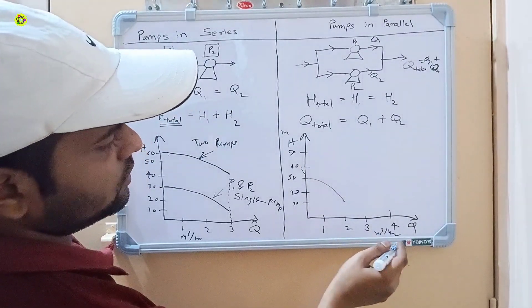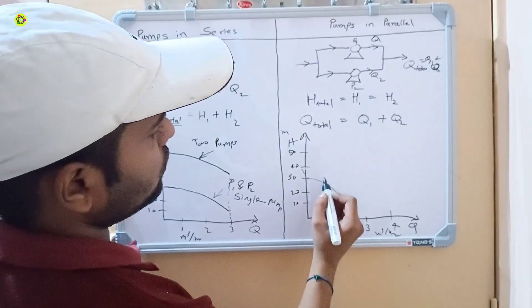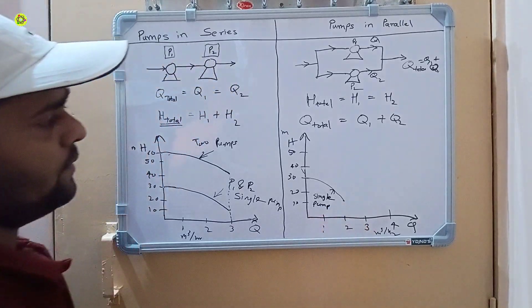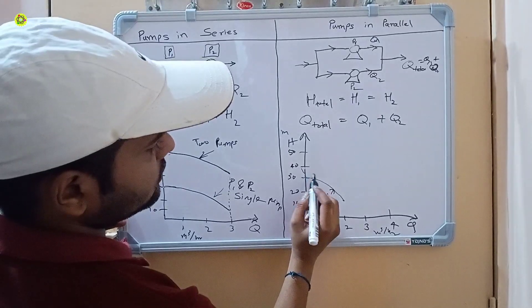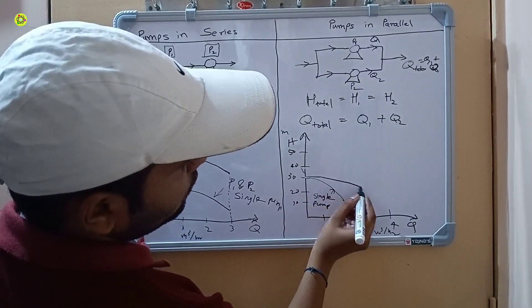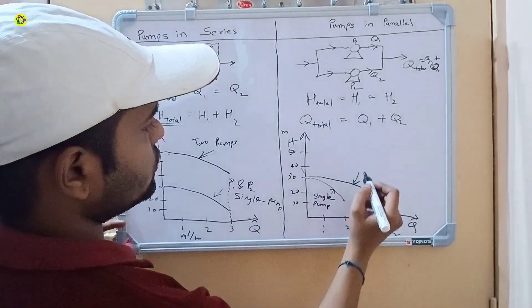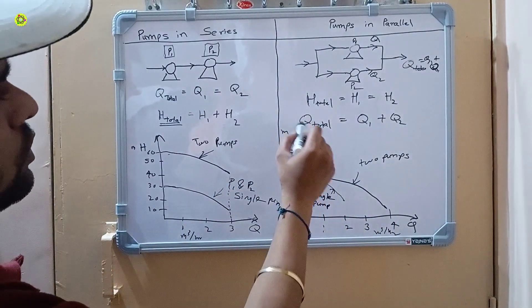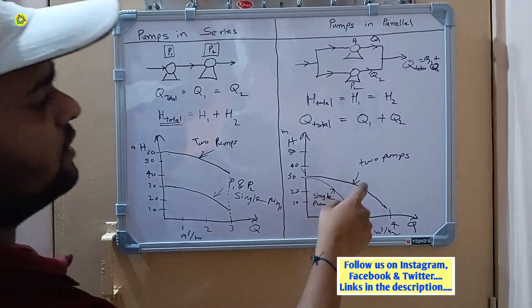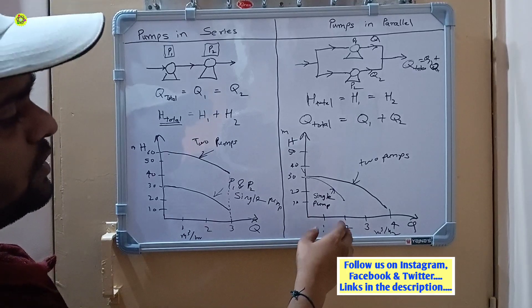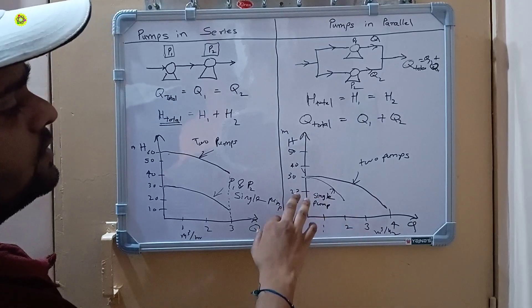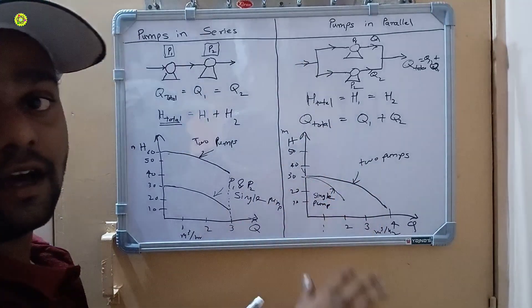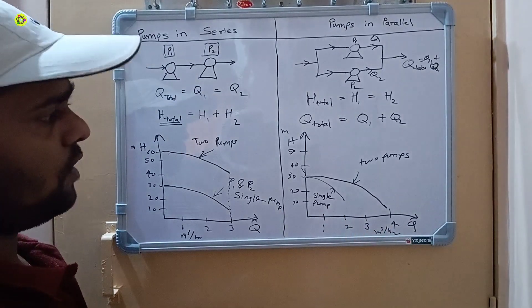For a single pump, the flow rate is about two meter cube per hour. For two pumps in parallel, the head remains constant but the flow rate increases to nearly double — approximately four meter cube per hour. Q total equals Q1 plus Q2, as shown on the curve for two pumps.